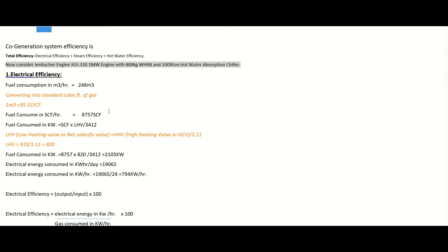Now I want to calculate fuel consumed in kilowatts. The reason is that the output of my gas generator is in kilowatts, so I need to calculate the input in kilowatts as well. The formula is: standard cubic feet multiplied by the low heating value, divided by 3,412.